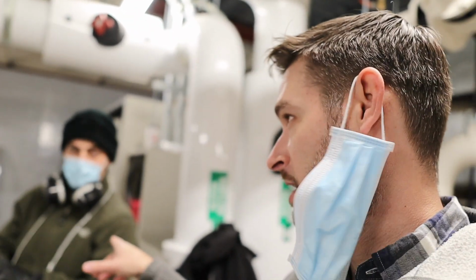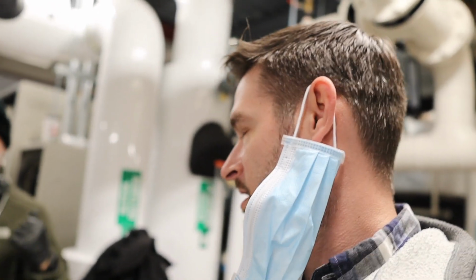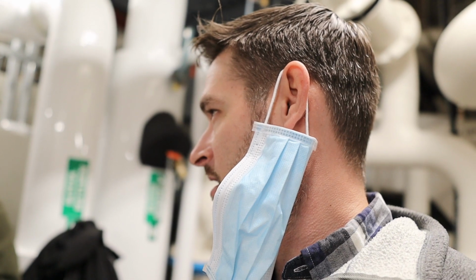This is Dennis from JPII, our tech. Okay. And our entering for the condensing side, for the heat pump loop, is designed 67 entering and 77 leaving. Perfect. So worst case conditions, after this thing's been running, the loop field's coming in at 38, leaving at 77. So we're just feeding a little bit of warm water out to the heat pump loop that's existing in the building. Now those heat pumps were replaced, but they had the existing loop already there. So we're just feeding out to that part of the building with 77 degrees, and then those heat pumps are going to extract that energy, and through their individual refrigeration circuits will heat, and when it's flipped over, they'll cool each of the individual zones, the classrooms and such.